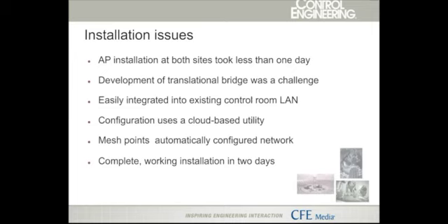Installation was also a big money saver. We were able to get the entire network up and operating within 2 days. The bridge, the translational bridge, was a bit of a challenge, and that required some development offline. But once we had that figured out, the entire installation was up and operating by the end of the second day. And it was easily integrated into the existing control room LAN using a simple switch.